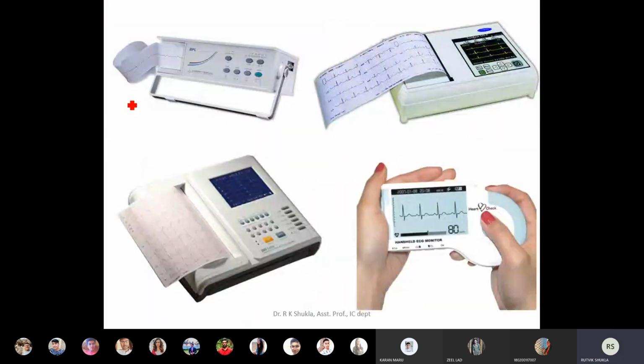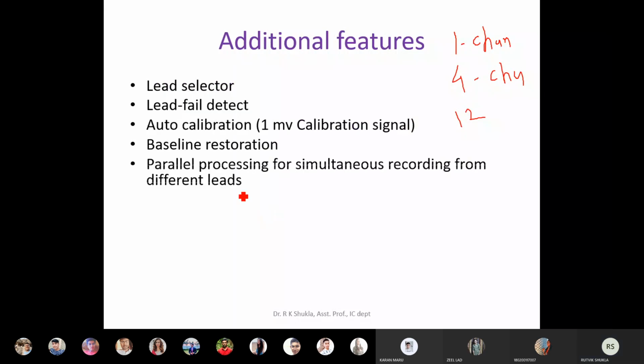Yeah, it's here. Look here, this is called a single channel machine because you can see only one channel at a time. This is a 4 channel machine because you can see 4 leads at a time, and this is called a 12 channel machine because you can see 12 different leads at a time. On its base, three different channels are written here: 1 channel, 4 channel or 12 channel. Now when you keep 12 channels or more than one channel, you need as many processing blocks as one channel needs. If you want to see 12 channels at a time, it means you require parallel processing blocks for that particular channel. Suppose one amplifier is needed for one channel, then for dual channel you have to use 2 amplifiers. For 12 channels you have to put 12 amplifiers.